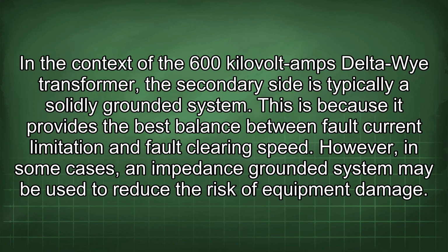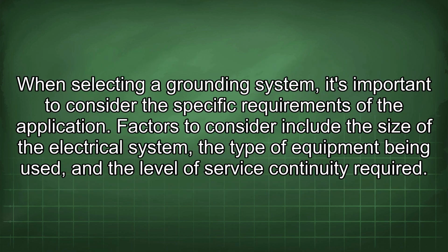In the context of the 600 kVA delta-Y transformer, the secondary side is typically a solidly grounded system. This is because it provides the best balance between fault current limitation and fault clearing speed. However, in some cases, an impedance-grounded system may be used to reduce the risk of equipment damage. When selecting a grounding system, it's important to consider the specific requirements of the application. Factors to consider include the size of the electrical system, the type of equipment being used, and the level of service continuity required.